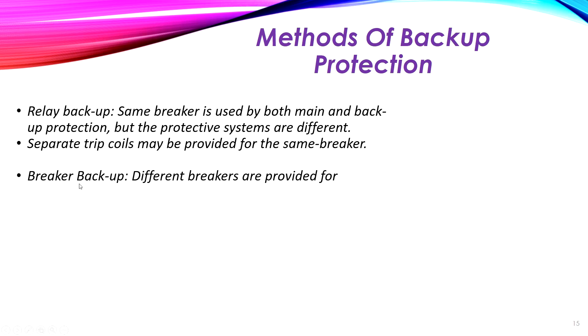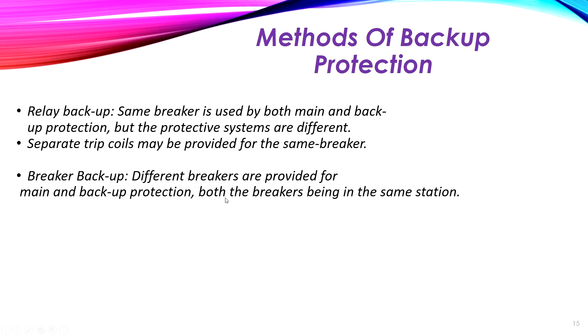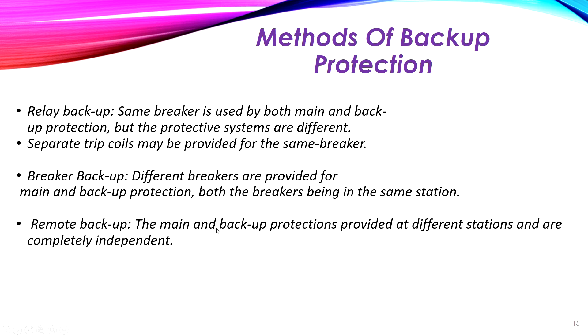The second type is breaker backup. In relay backup we back up the relay, but in breaker backup we add an additional circuit breaker. Different breakers are provided for the main and backup protection, both breakers being in the same station. So we have two breakers — one which is the main protection breaker and the second is the backup breaker. If the main breaker did not work, the backup one will trip the circuit. For remote backup, the main and backup protections are provided at different places or stations and are completely independent from each other.